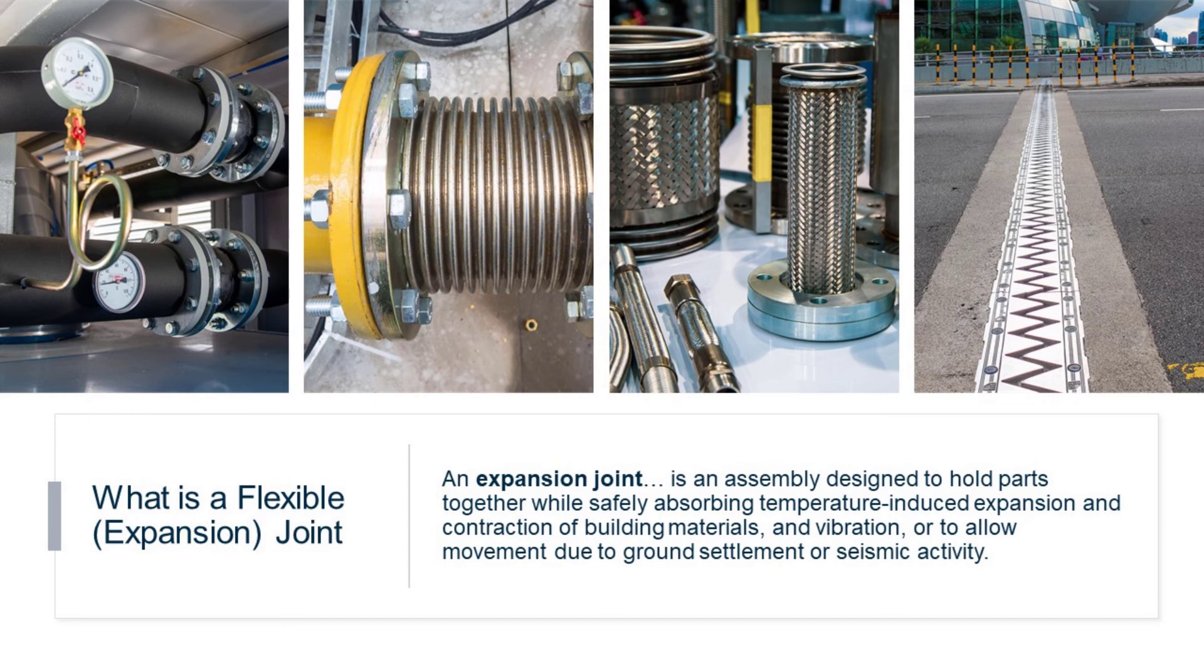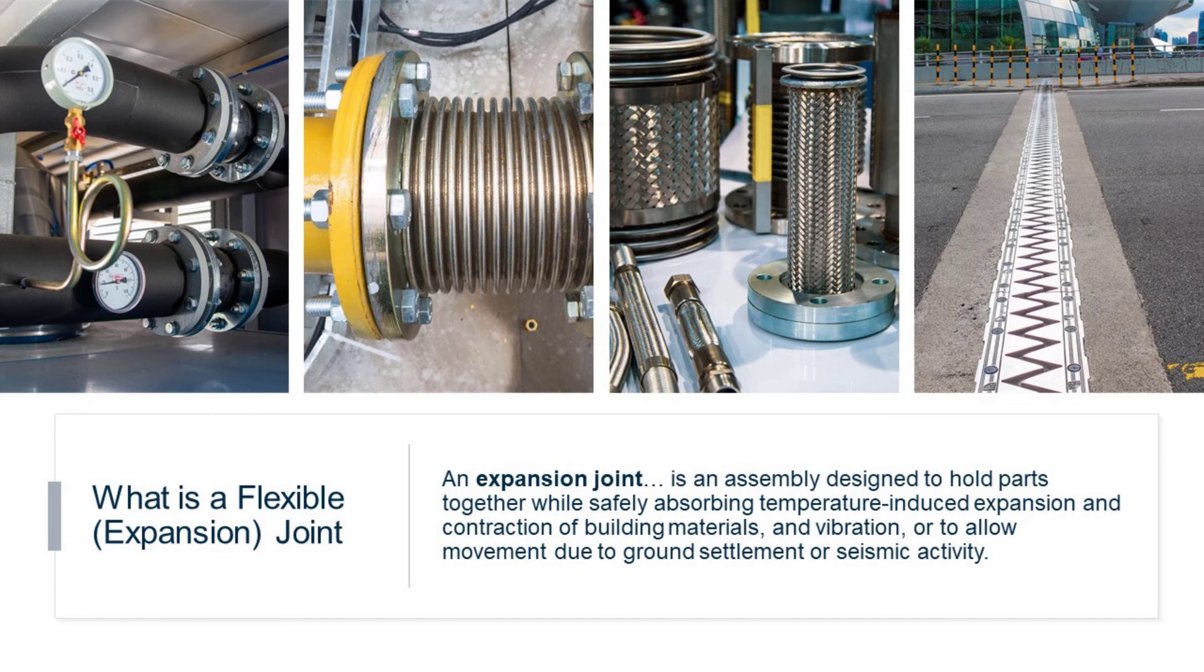Expansion joints also have a low cycle fatigue life, so hard piping is usually a safer option in potentially lethal situations such as a hot steam line. However, there are many instances where there is not enough space to insert a pipe loop large enough to supply the necessary flexibility or you may have other reasons why you decide or choose to use an expansion joint, but not enough space is a common reason why the need for expansion joints arises.